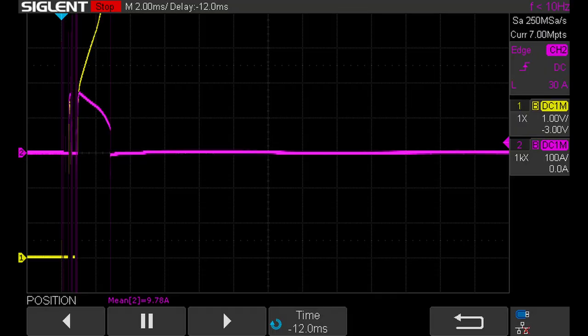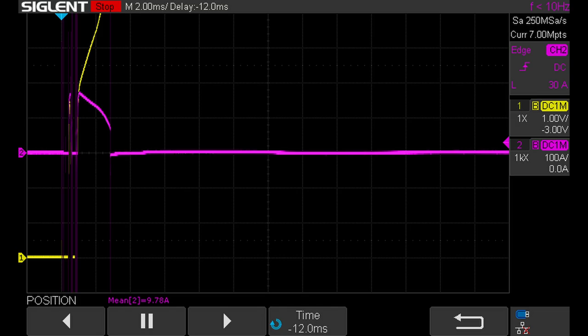The scope trace seems to confirm the shorter arc. The fuse blew in less than 3 milliseconds. The maximum current through the circuit is less than 200 amps, and it drops off very quickly as the fuse resistance goes up. This still may not prevent any additional damage to your equipment if something fails, but it will certainly help.